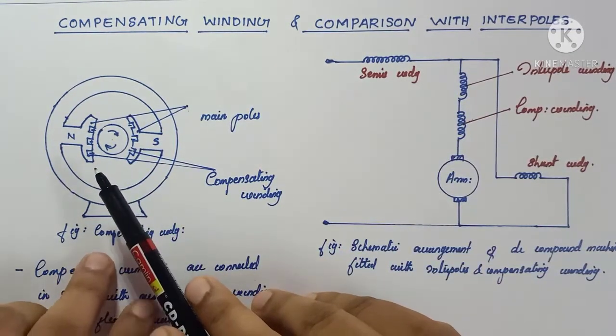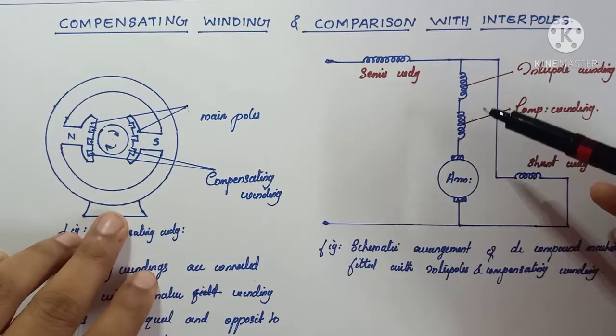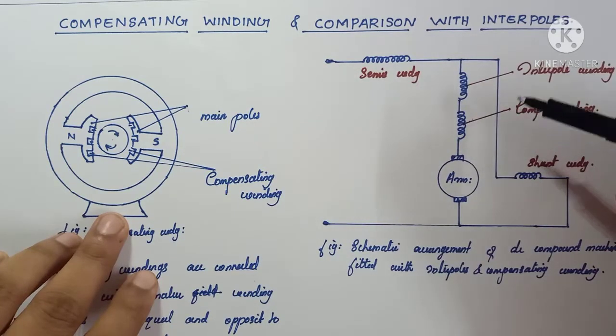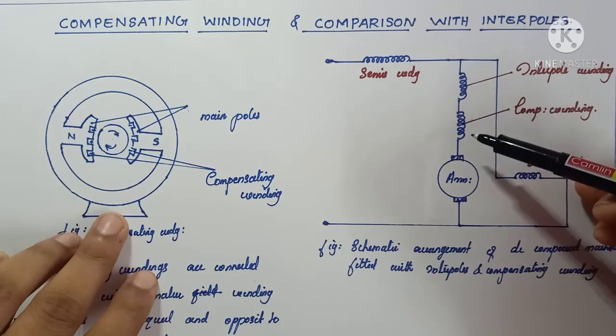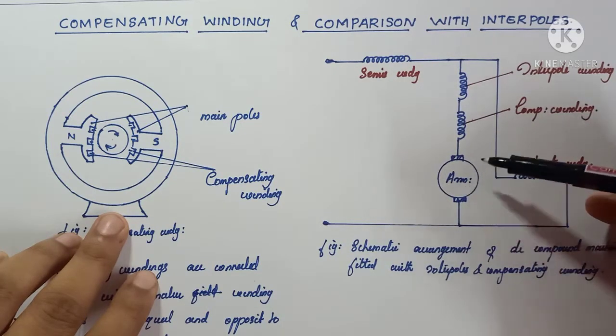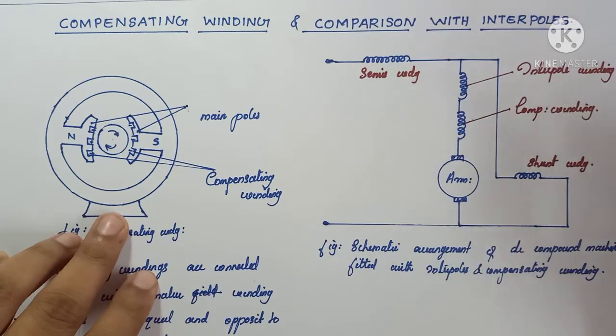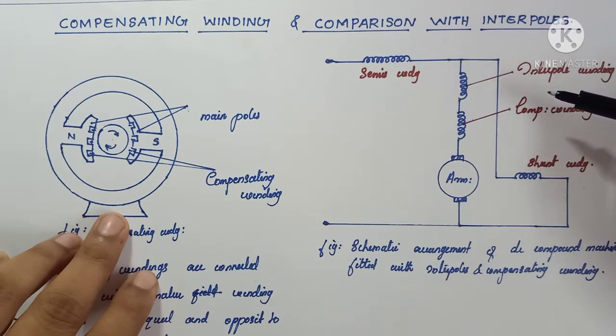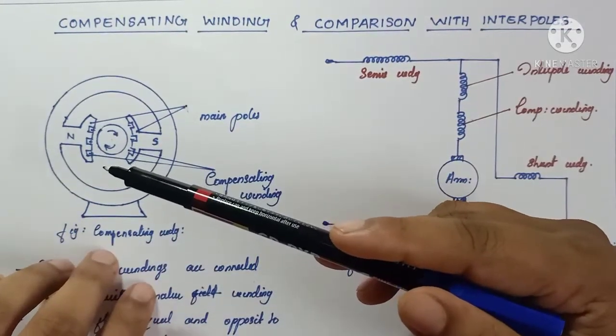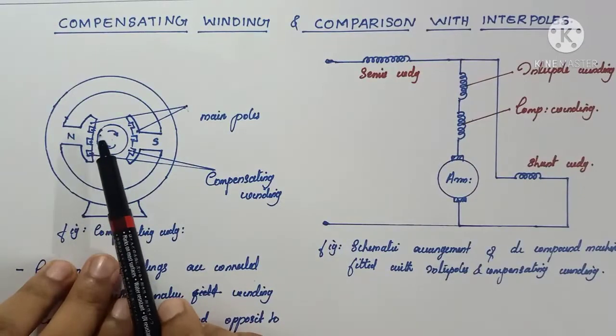Armature reaction is reduced by compensating windings, and since they are connected in series with the armature windings they also help to reduce poor commutation — providing further support to the interpoles for good commutation in DC machines. Both the interpoles and compensating windings can be used to improve commutation, and compensating windings will also reduce the demagnetizing effect of armature reaction.